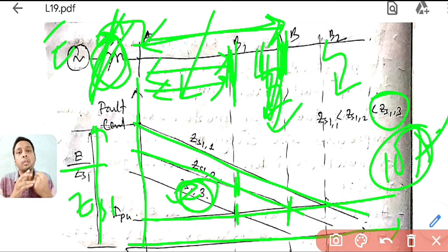So the relay underreaches. Similarly, if you decrease ZS, it will go up to here, because now it has the flexibility to go further, since your source impedance is less and you are fixing a 10 ampere threshold. So to get 10 ampere, it can reach beyond your AB, so it can take more ZL. So ZS plus ZL remains fixed, because ZS is reduced.